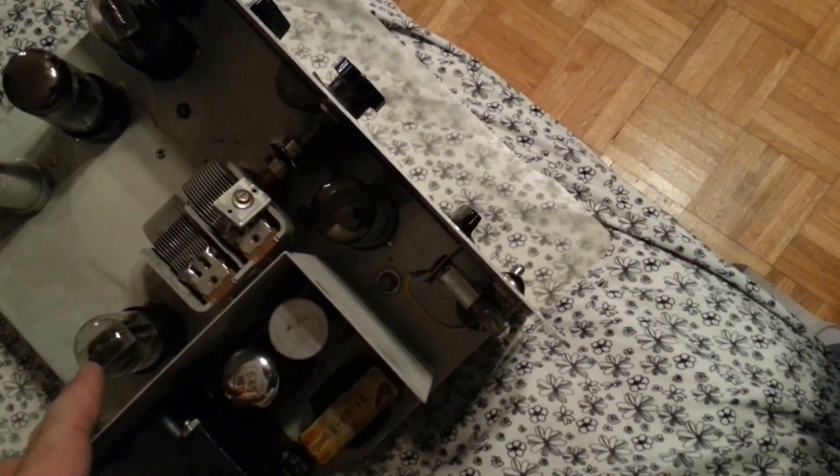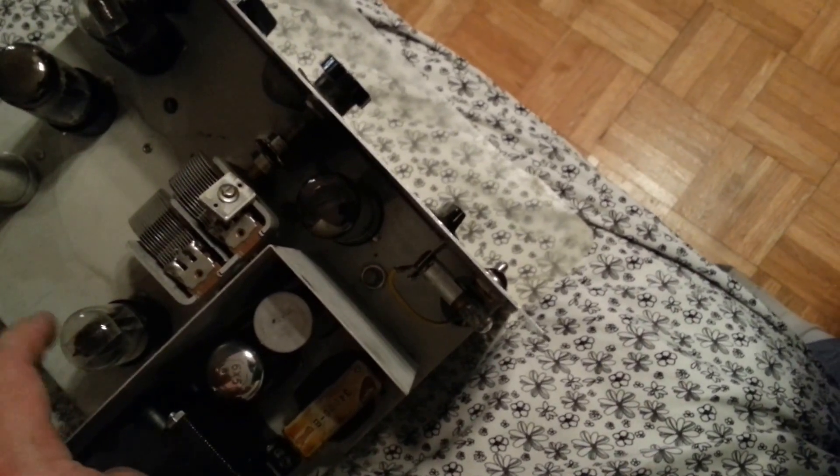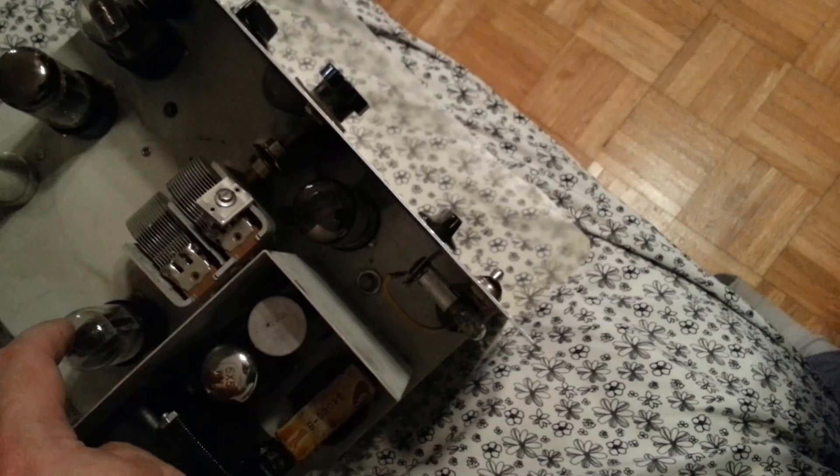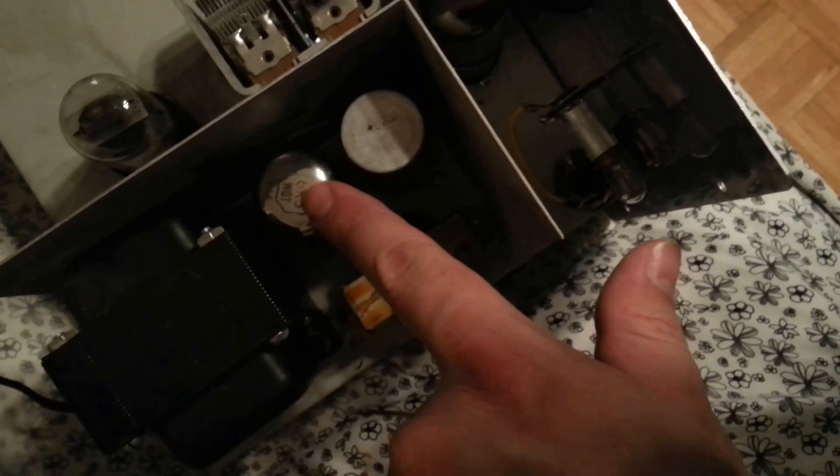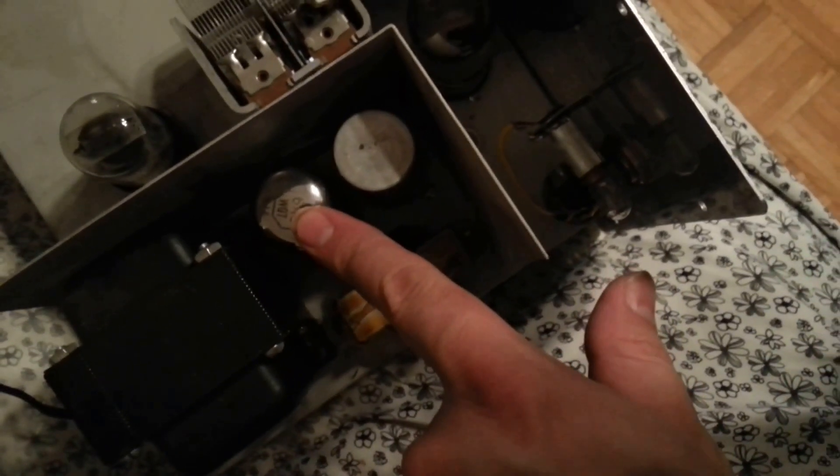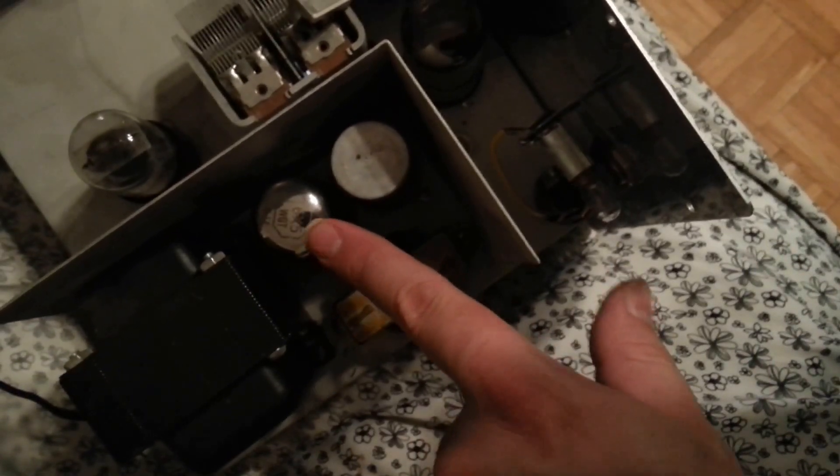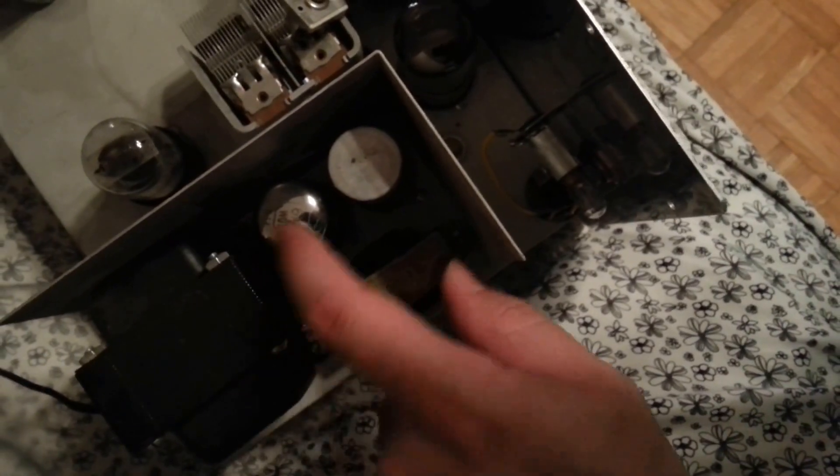This tube here is the pre-amplifier. This is a 6J6. I'm going to replace this tube later on because as you can see this thing has a good amount of filament boil off. This 6X5WGT rectifier is also new. This is an industrial grade 6X5 which is highly recommended for anyone who has an instrument or anything else that uses a 6X5.